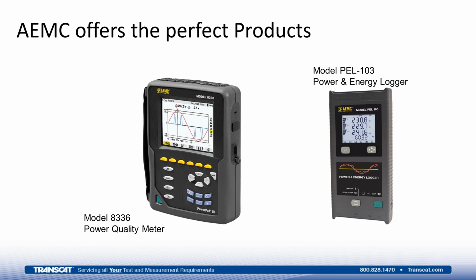This one looks at waveforms and everything else in addition to the energy. For those people who are interested, it does things like harmonics, and it does transient detection and a few other things. The one on the right is referred to as a power and energy logger. It is designed to primarily measure watts, vars, and VA, and measure that energy over time, doing the watt hours, the var hours, and the VA hours.